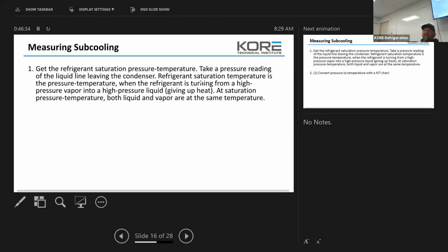But what type of systems am I going to actually go after subcooling instead of superheat? HVAC, yeah. When you're dealing with high temp, most high temp manufacturers are going to tell you to check the subcooling, not so much the superheat. Okay. So you need to understand how to do both because you work on both.